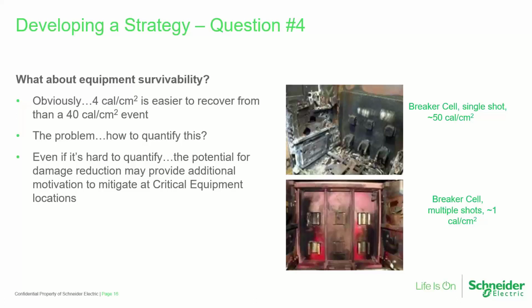Above that, you have to replace the equipment. We just don't know. Common sense, though, tells you that if you've got a 4 calorie per centimeter squared event, it's going to be a lot easier to recover from than a 40 calorie event. And so in some cases, we've had discussions with folks in high availability type facilities, critical data centers, and hospitals, and this kind of criteria, equipment damage, becomes part of the consideration as well. And so that can lead you to maybe target lower energy levels than just getting it below 40. If we get it to 39.8, maybe we're not happy if this is one of our major drivers.